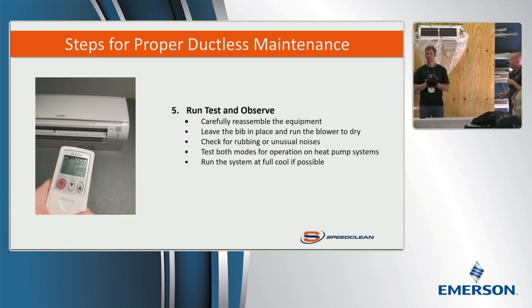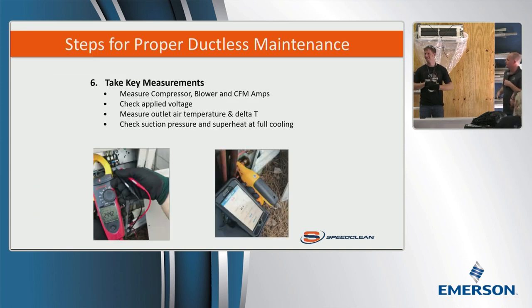Okay, so run, test, and observe. Take key measurements. We're going to go over what some of these are, but we already talked about discharge air temperature being one of the best. Suction pressure and superheat at full cooling can be valuable, but mostly it's just telling you you're looking for a really low number, in some cases even zero. A lot of manufacturers are going to tell you not to do it at all because they don't want you messing with the charge.